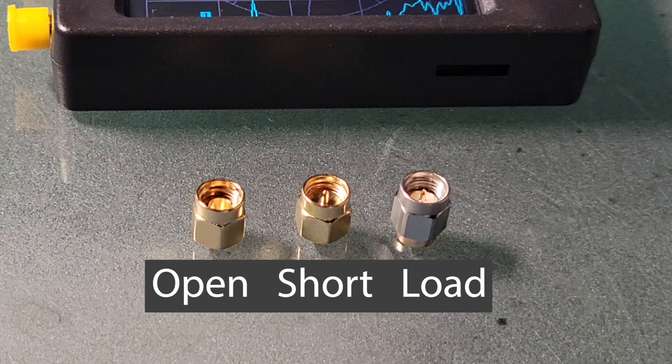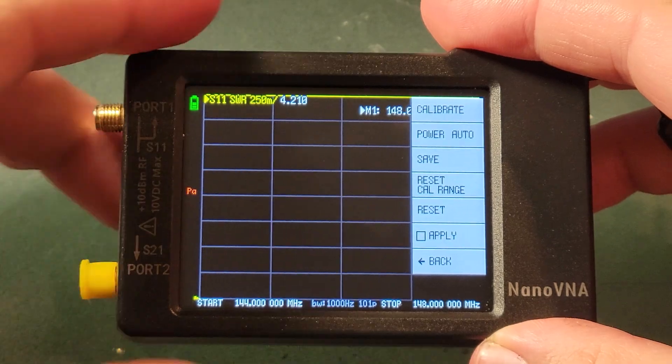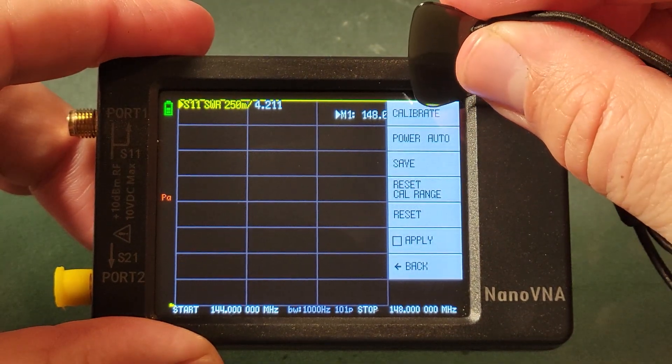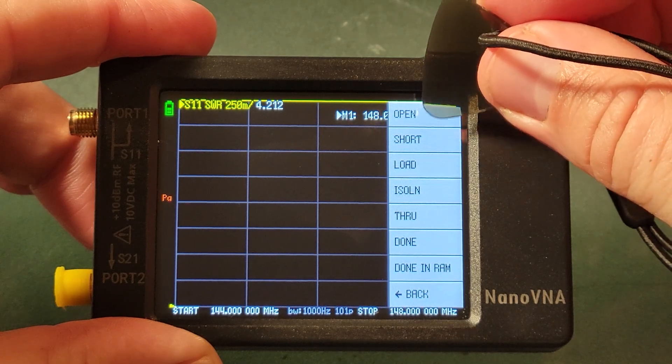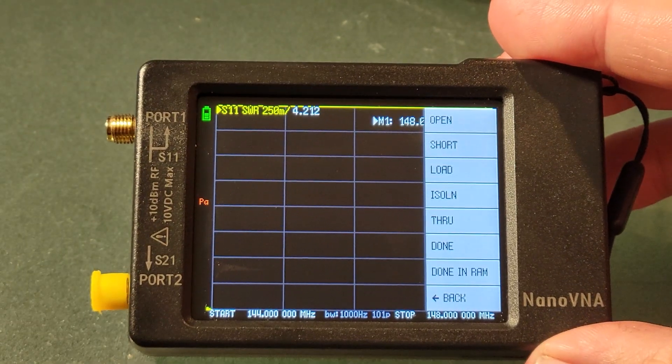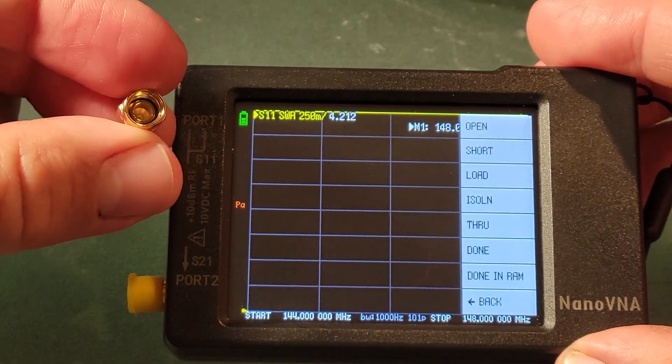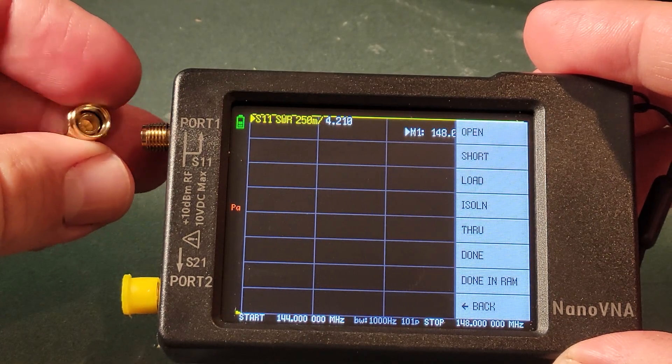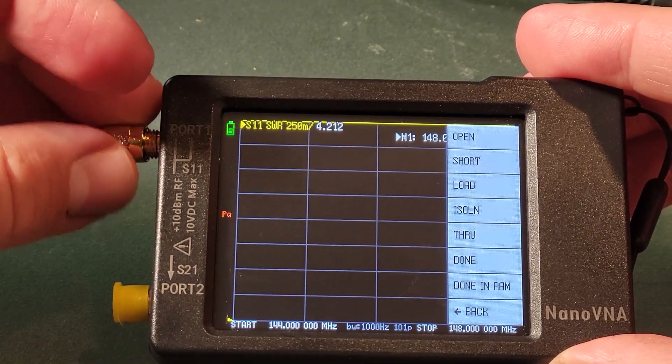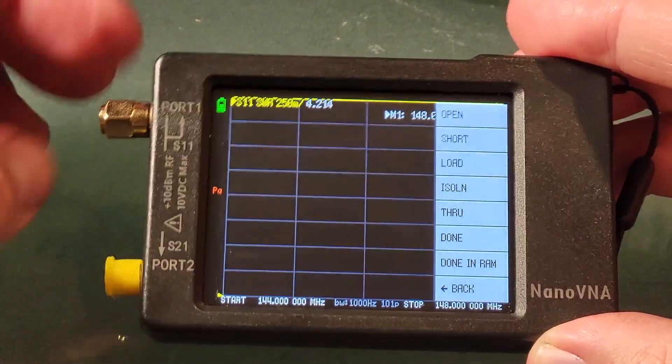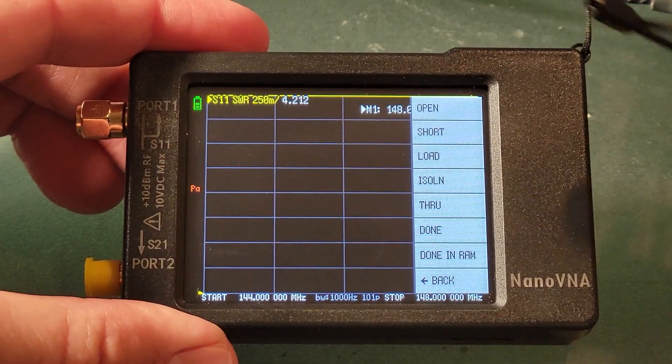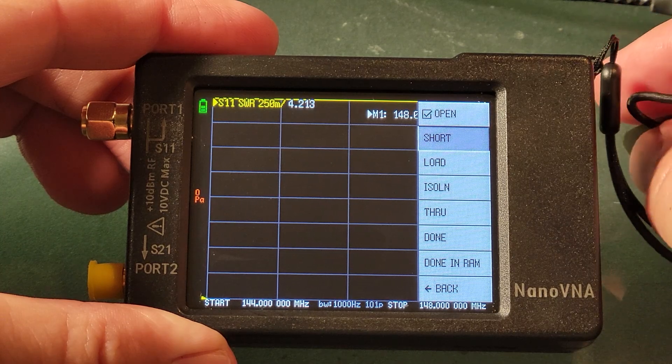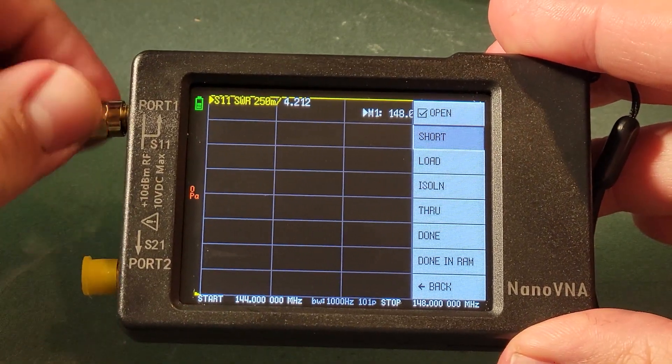We will be starting with the open and you can see the correct order to do this by digging a little bit further down here in the menu to calibrate and it'll tell you open, short, and load. So we'll start with our open. Notice that this cap does not have a pin in it, also known as the open. So we'll thread that on quickly and we will tap the open button with our guitar pick and watch at the very top of the screen as I do that a blue line goes across there giving you a progress and we get a check mark indicating that that task is complete.